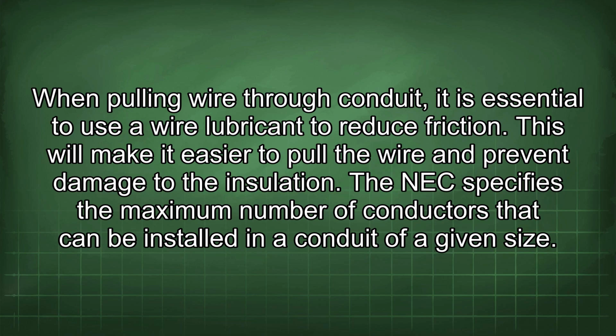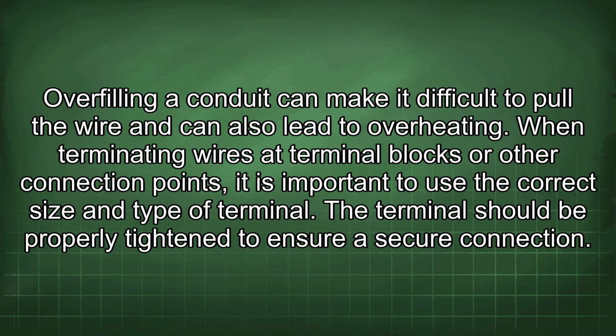The NEC specifies the maximum number of conductors that can be installed in a conduit of a given size. Overfilling a conduit can make it difficult to pull the wire and can also lead to overheating. When terminating wires at terminal blocks or other connection points, it is important to use the correct size and type of terminal.